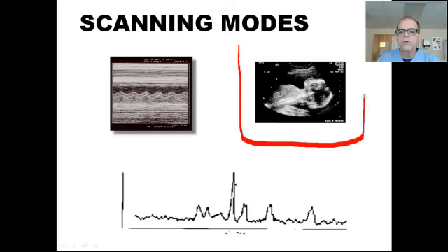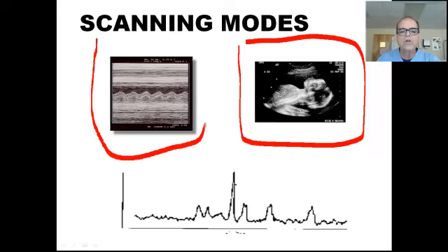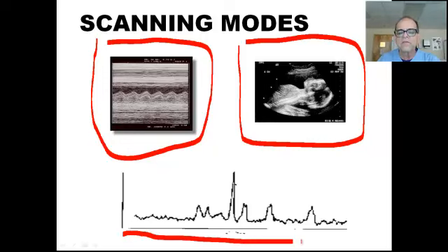B mode. The other mode that we use, which is not as important as B mode, is the motion mode, and the last one, the A mode, is something that is only used in ophthalmology. It's not something that you can do with the normal ultrasound machine that we use in hospitals. It's a special ultrasound and it's called A mode.